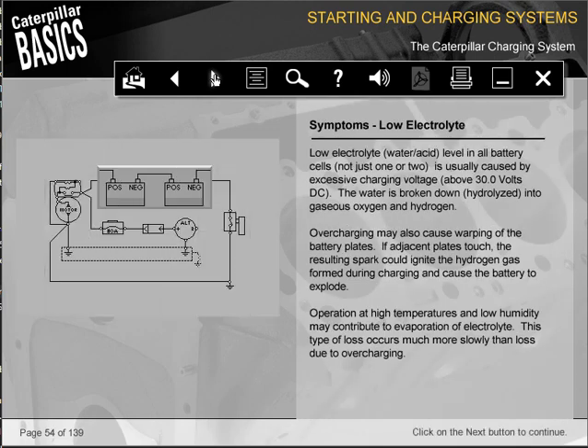Low electrolyte, meaning the water and acid level is low in all battery cells, not just one or two, is usually caused by excessive charging voltage above 30.0 volts DC. The water is broken down, hydrolyzed into gaseous oxygen and hydrogen. Overcharging may also cause warping of the battery plates. If adjacent plates touch, the resulting spark could ignite the hydrogen gas formed during charging and cause the battery to explode. Operation at high temperatures and low humidity may contribute to evaporation of electrolyte. This type of loss occurs much more slowly than loss due to overcharging.